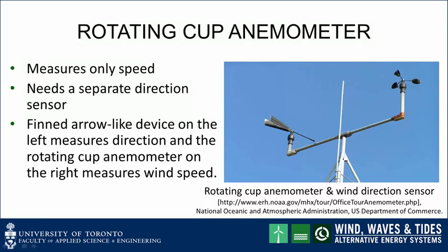A second type of wind measuring device is the rotating cup anemometer, shown on the right. This device measures only wind speed and isn't direction sensitive, so there is a sensor here to measure the rotating speed. The finned arrow-like device on the left measures direction. The fins keep the sensor pointed into the wind, and a rotary position sensor in the pivot provides wind direction information.